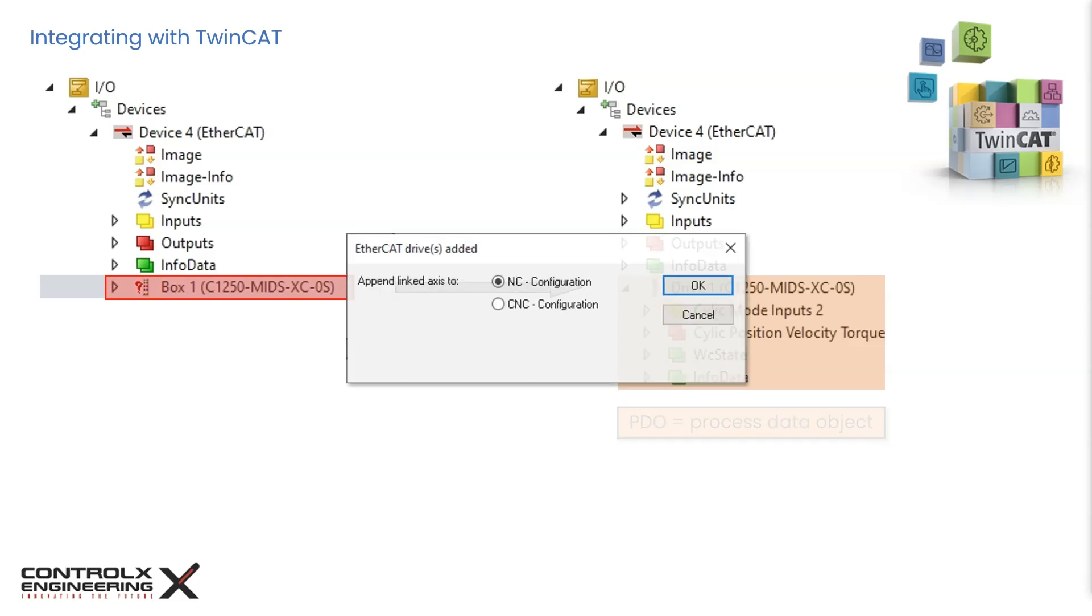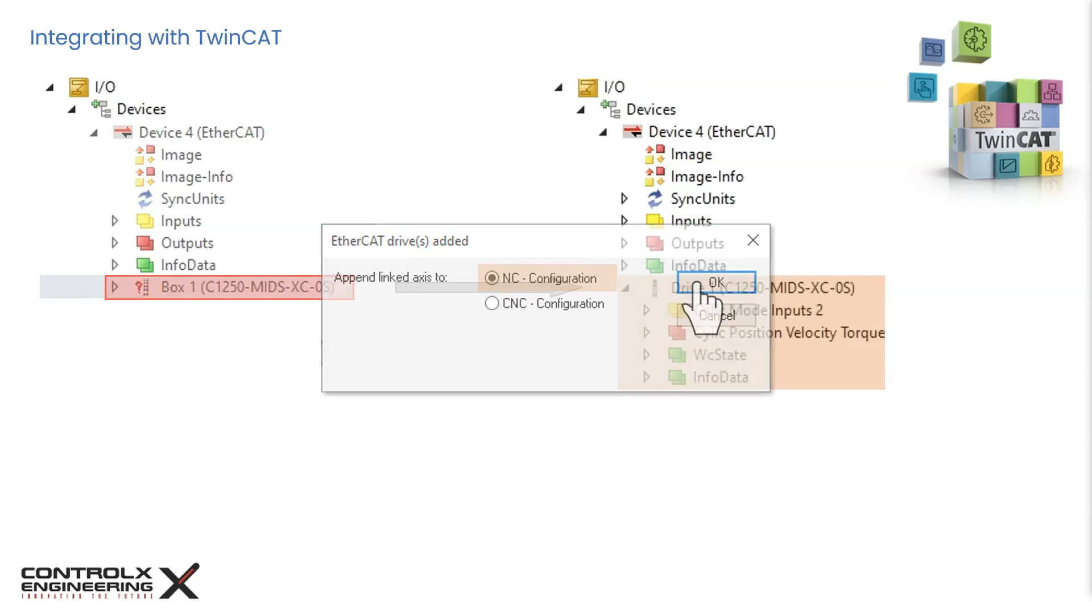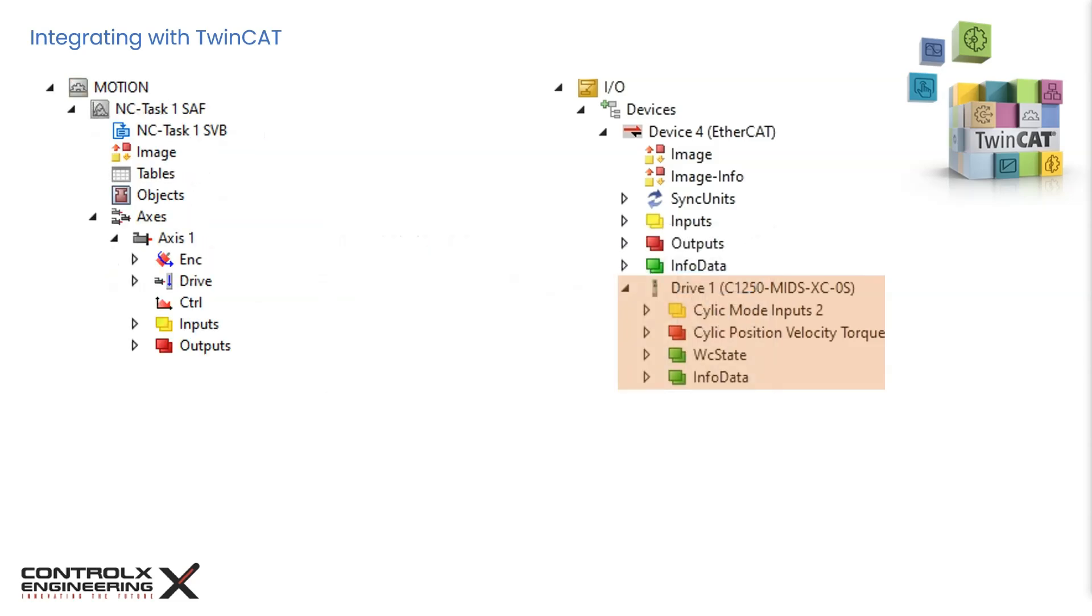In addition, since TwinCAT recognizes the slave device as a drive, it is now asking whether the drive should be appended to the motion node in NC or CNC configuration. For our application we'll select NC configuration and click OK. The new LinMot drive is now appended to the motion node as an NC axis and automatically labeled as axis 1 since this is the first axis we added to the configuration.